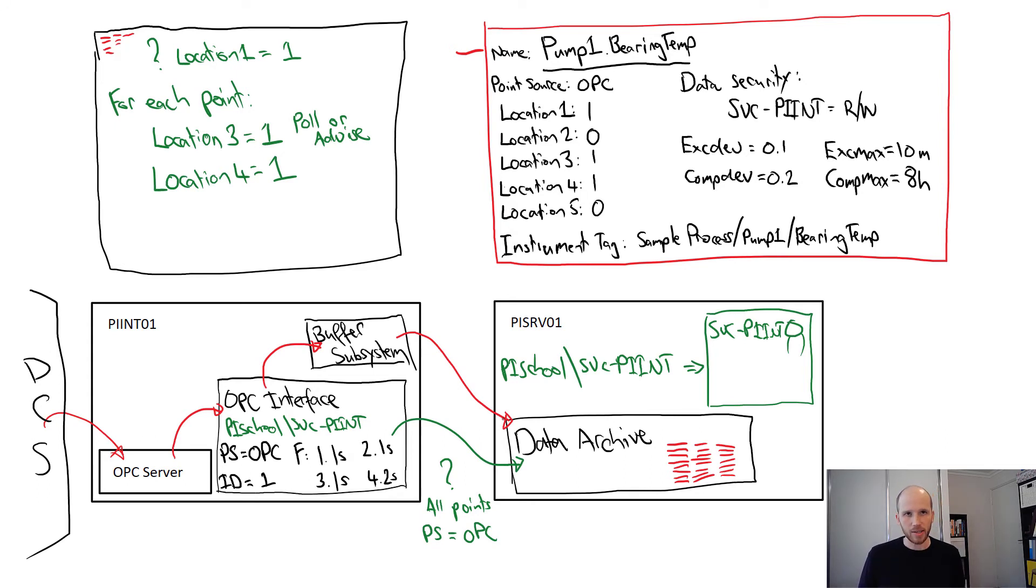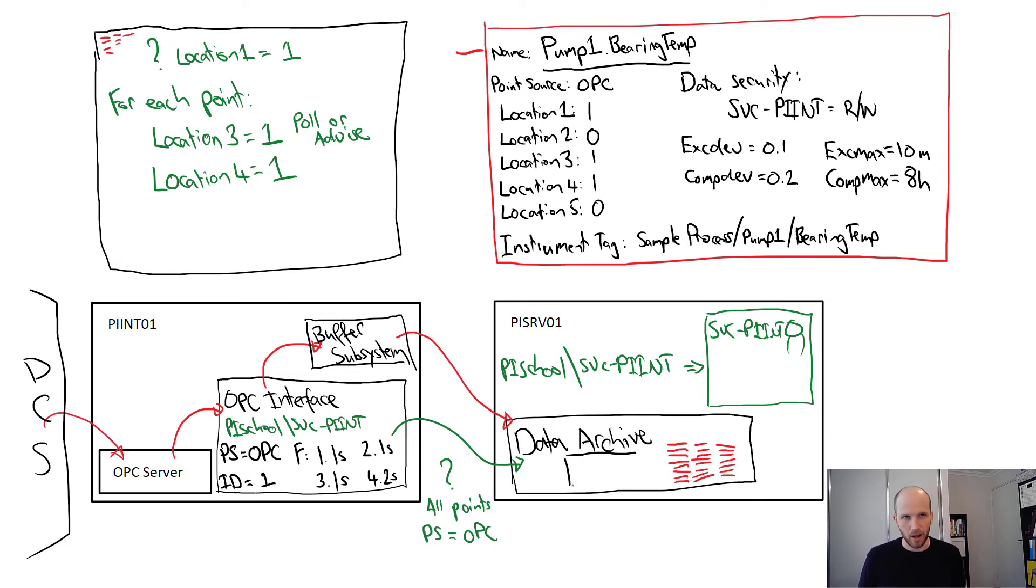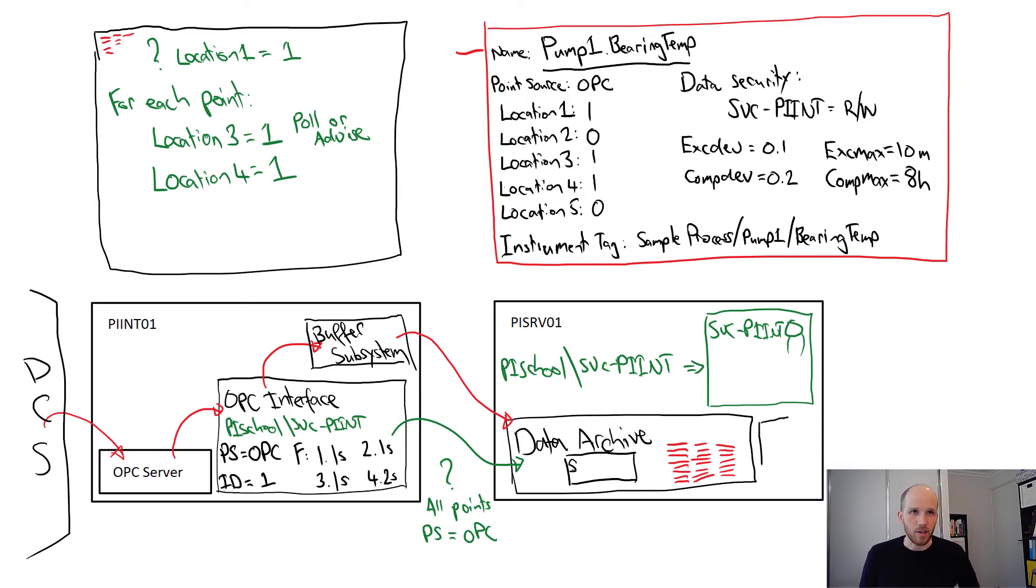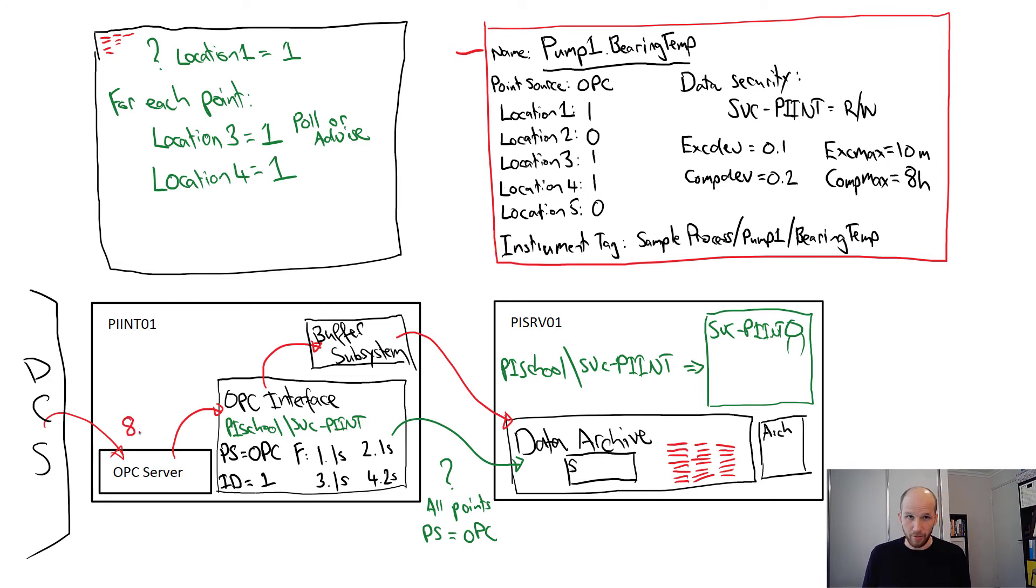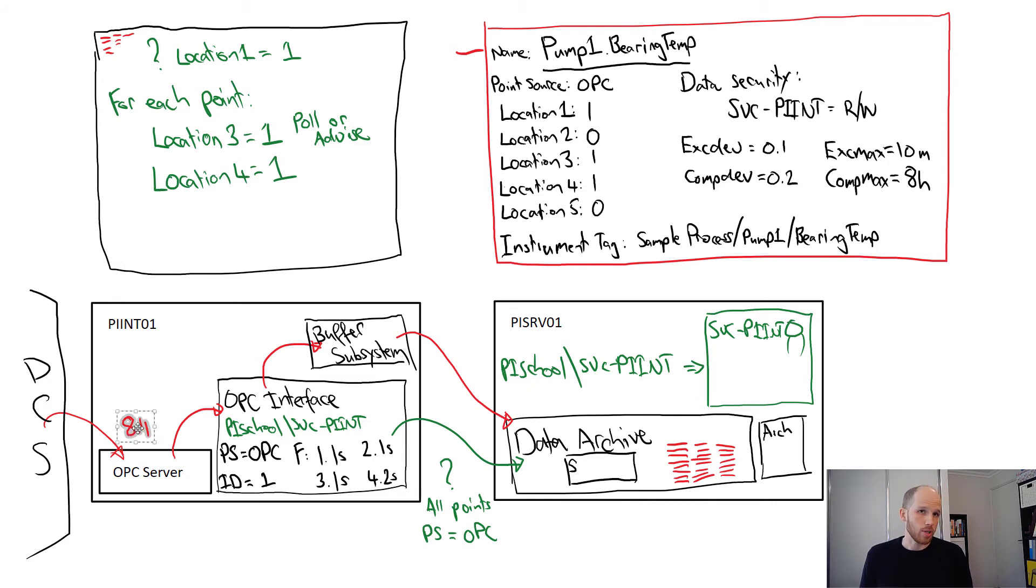Let's take a little look at how data is handled here. The data archive has a spot in memory and a memory map file for the current value of every tag. It's called the snapshot. It also has the files on disk for historical data for tags called archives. The OPC server has a new value for bearing temperature. It's 8.4. We call this value an event. The OPC server sends this through to the interface.